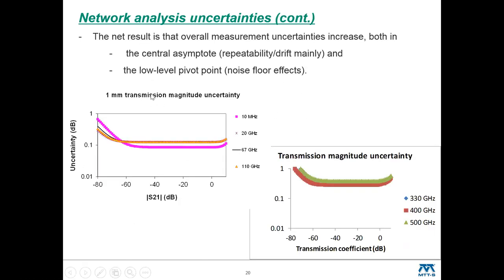So if one combines these to figure out a net transmission magnitude uncertainty, and this is a really simple model, it's plotted here. We have the transmission of the device you're trying to measure on the x-axis, and uncertainty on the y, for a couple of systems - our 110 gig system and our 500 gig banded system over here. You'll notice a few things structurally. There's this central asymptote, and things that go into that are calibration terms we talked about, which aren't too significant here, but also repeatability and drift, which tend not to be too level sensitive. That's gotten a bit worse - I can see that just from the scale.